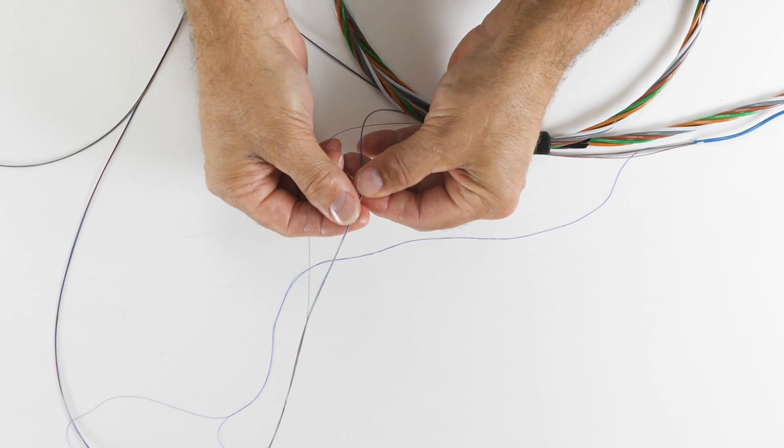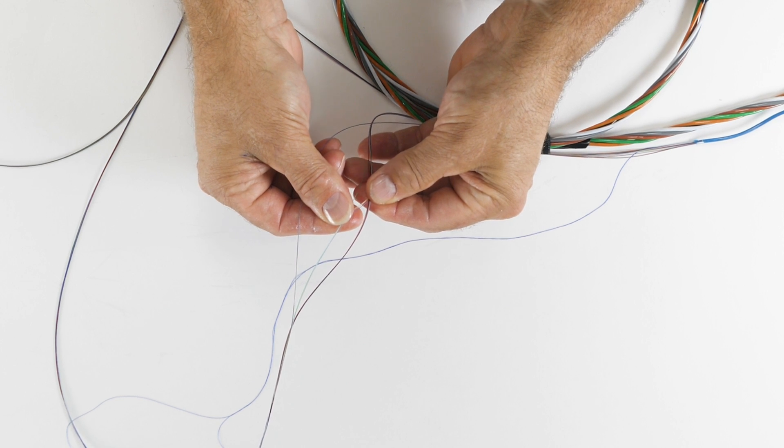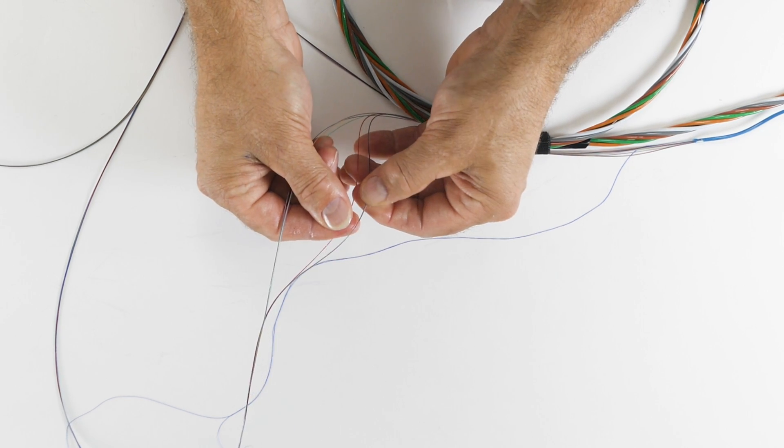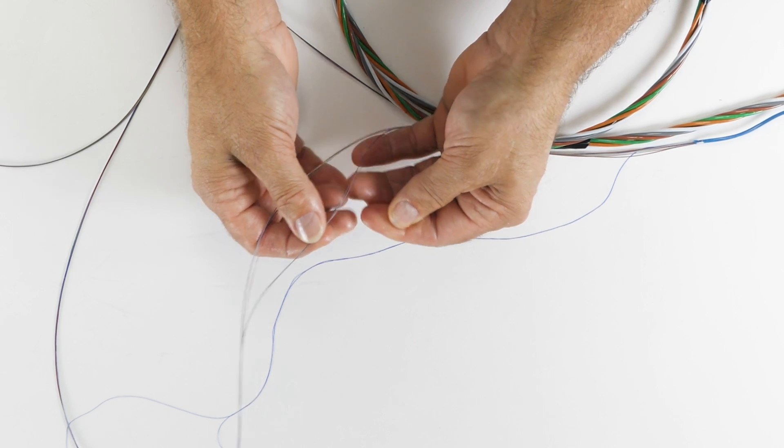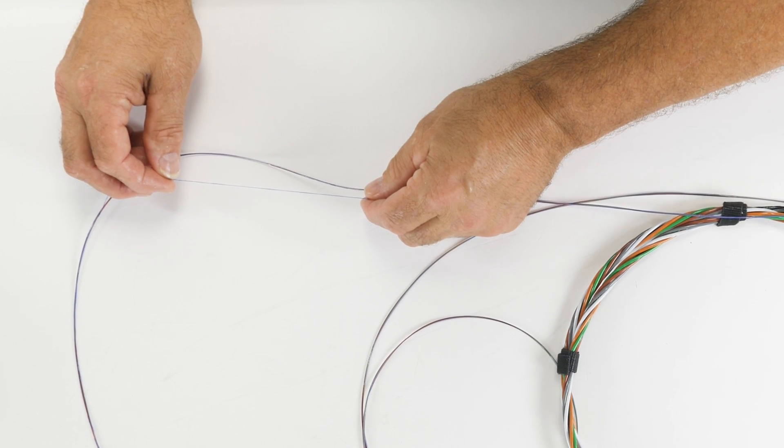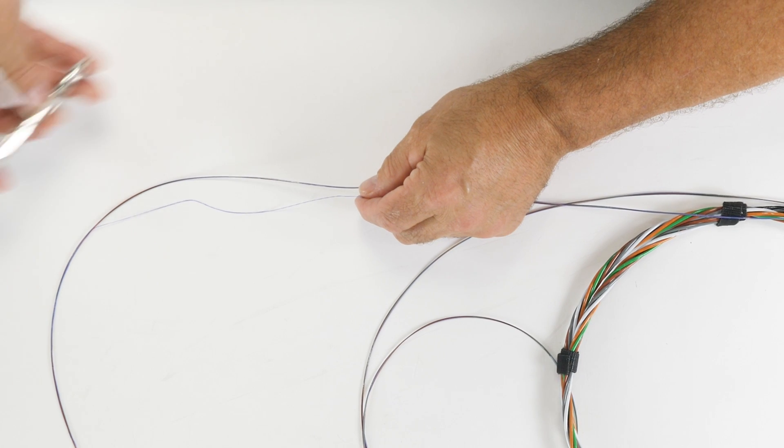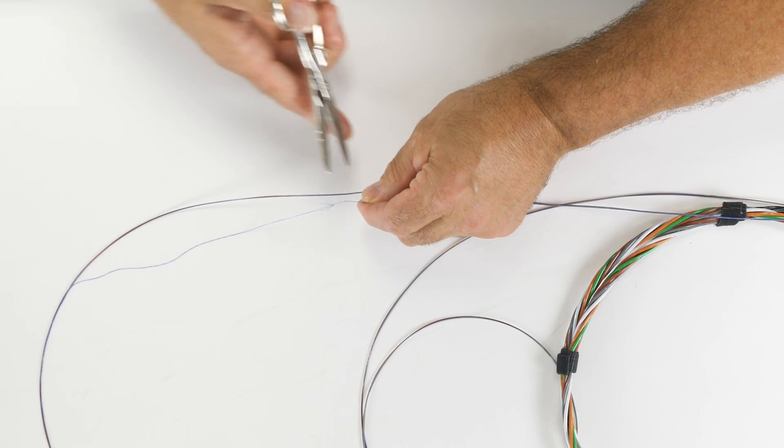Once the groups have been identified, count the number of fibers in each group and identify the color code before separating the entire length. Separate the blue binder group and cut the binder back to approximately 10 inches on each side.